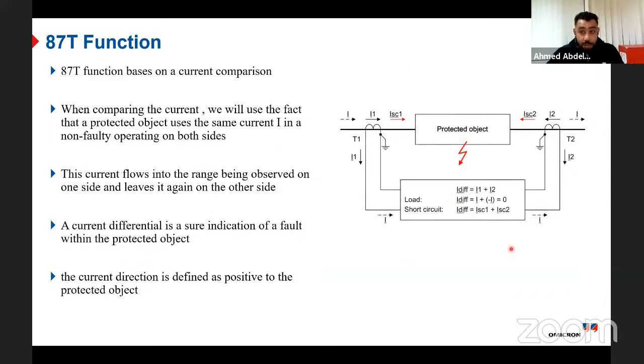Let us look at our system. If I have a fault in the protected object, as we all know, the current will flow in the direction of the fault. So I have a short circuit here. Current will go to the fault point from the right side, and current will flow from the other side to the fault. So both currents flow in the same direction. All of them are in, so this will be positive, and the other side will be positive.